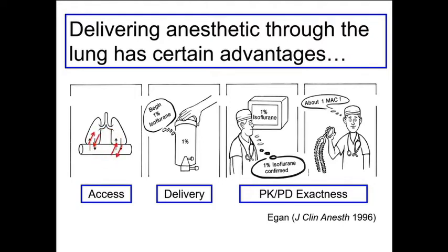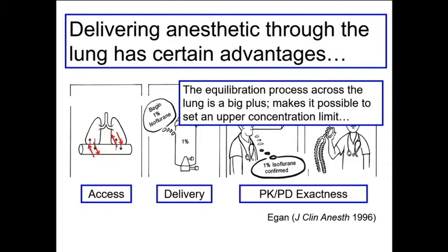In addition, you've got the ability to show that you've set some type of pharmacokinetic target with the vaporizer, and you can turn around and see with expired gas monitoring that that target has been hit. And back in the 90s, we had very good understanding of what the target should be. Every anesthesiologist thinks in terms of MAC fractions or MAC multiples for a given patient, a given anesthetic technique, and a given operation. So this equilibration process is a real plus because it makes it possible to set this concentration limit and makes it so we can practice in the concentration domain.